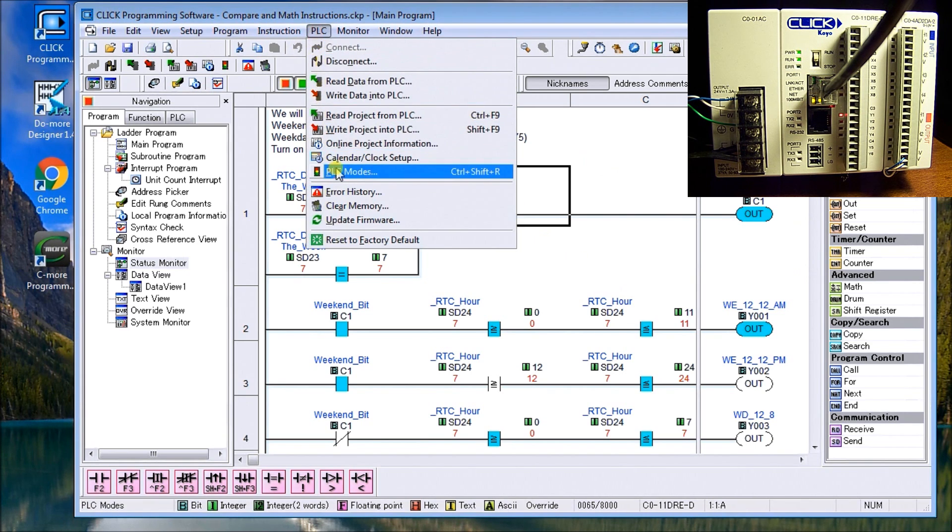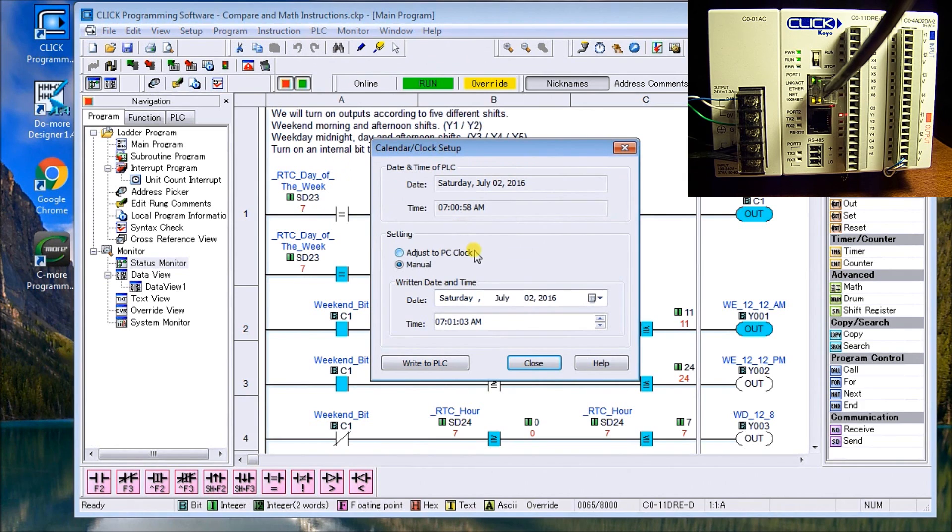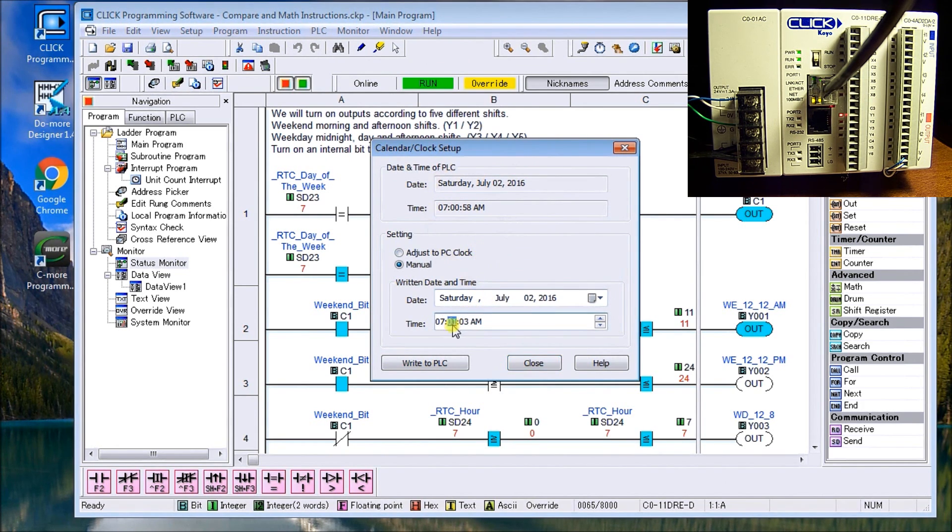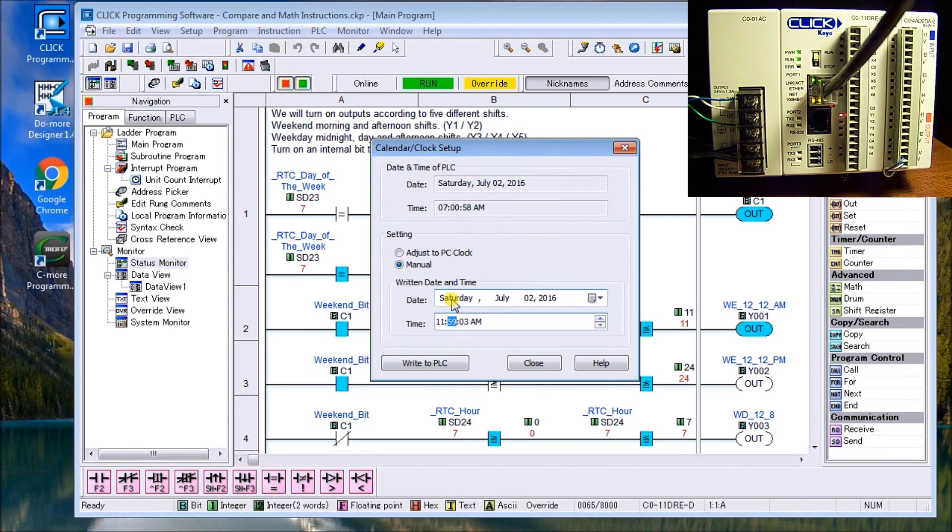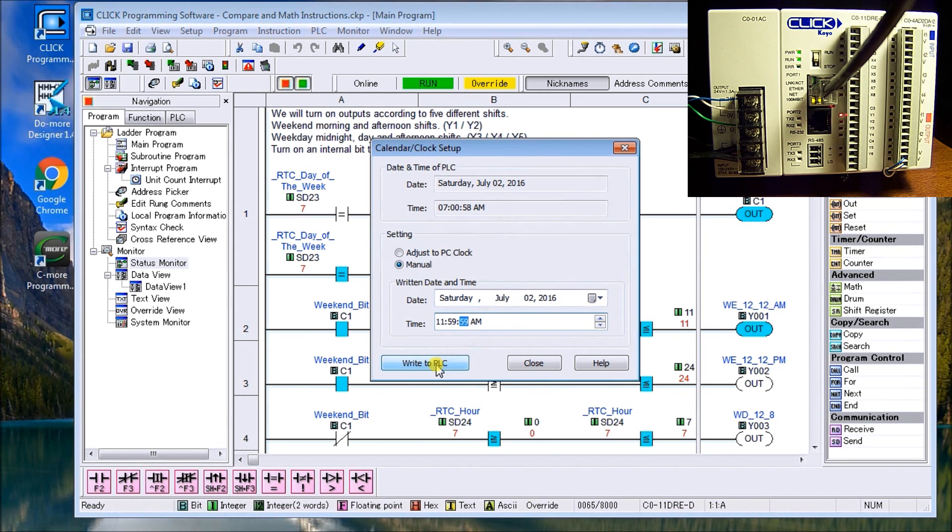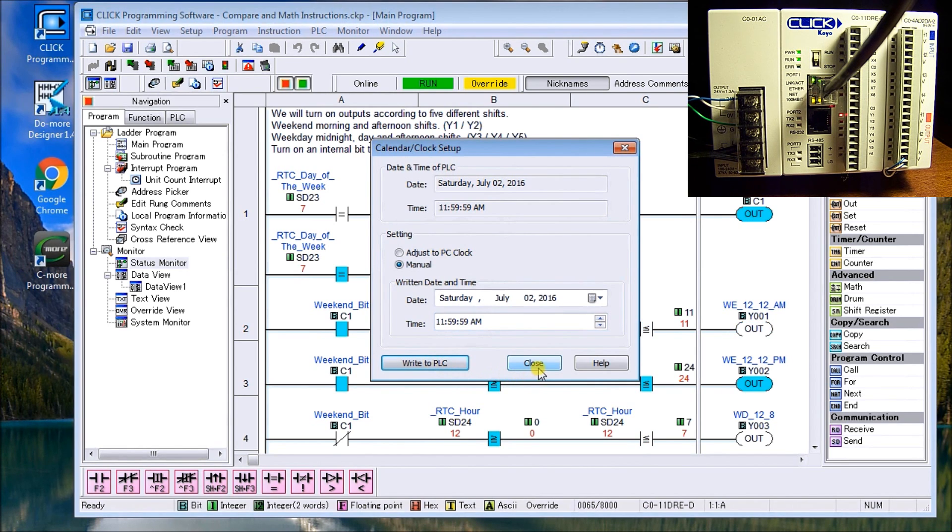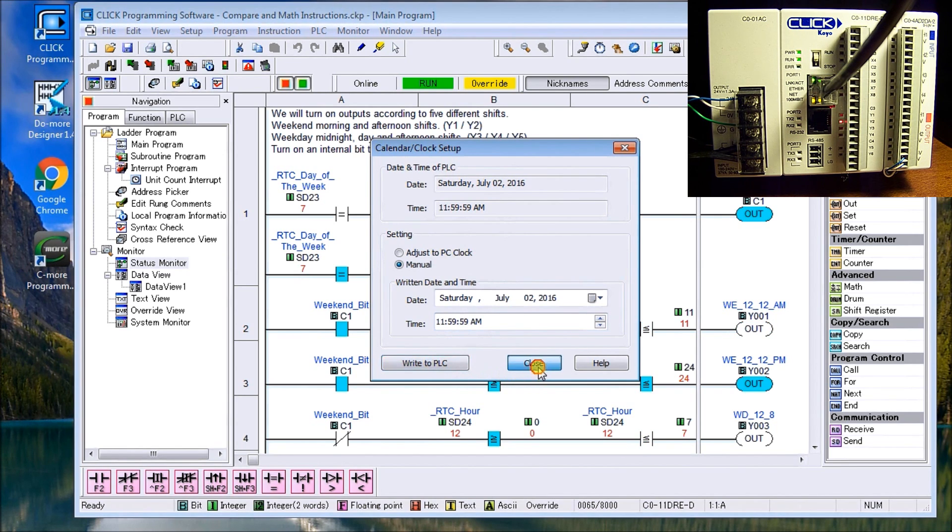Now if we go to the PLC, we go into the calendar and time clock. You'll actually notice that here's where we can actually change the value. So if we want to say, okay, let's just change that to 11, 59, and we'll go 59. And we're going to write that to the PLC. Then after a second, we should actually see that output change on our PLC. So we'll write that now. And you heard that click and you also change the output here.